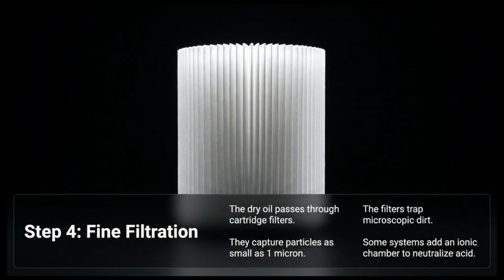In Step 4, fine filtration, the dry oil passes through cartridge filters. These filters trap microscopic dirt as small as 1 micron. Some systems also use an ionic chamber to neutralize acid.